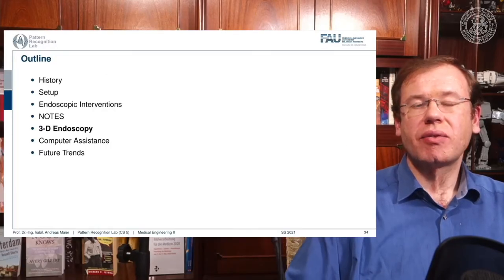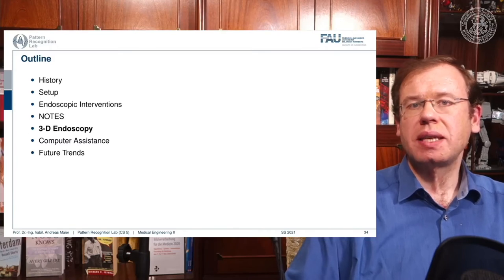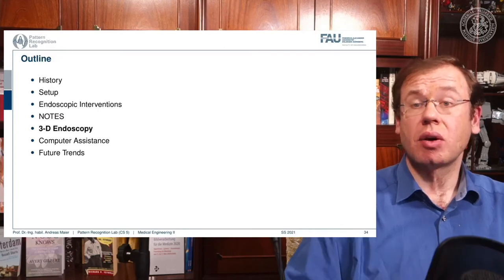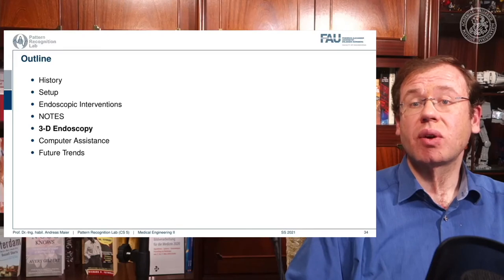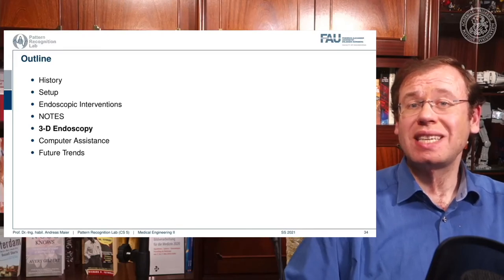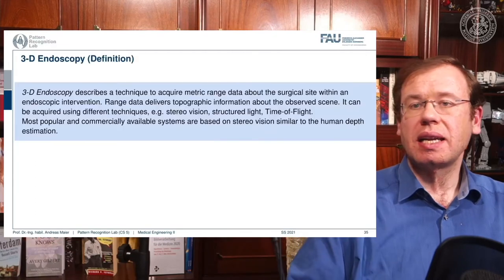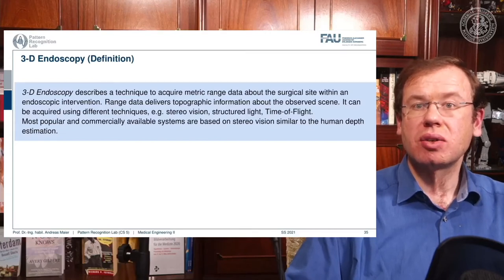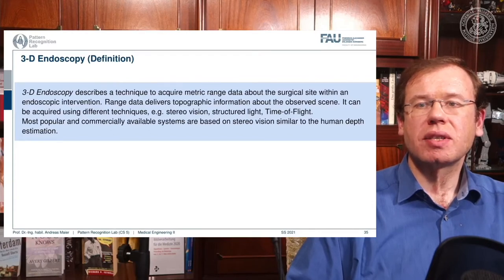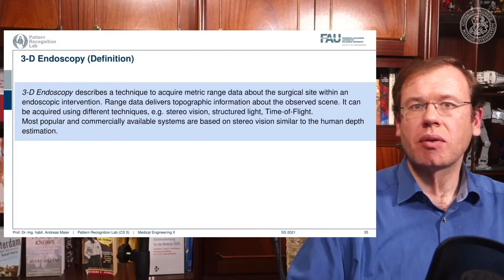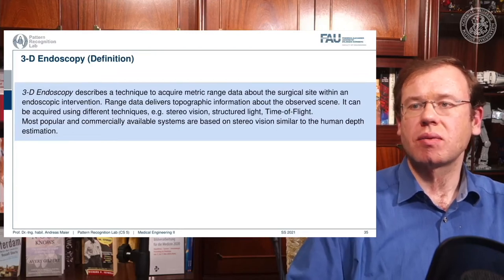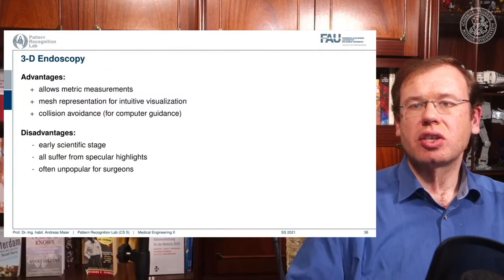Another very important topic is 3D endoscopy, which could be a game changer for complex interventions like NOTES. The idea is not just to see inside but to get a real 3D reconstruction of the tissues inside the body. In 3D endoscopy, we acquire metric range data — depth data like surfaces or point clouds of the surgical site — using an endoscopic intervention. This range data delivers topographic information about the observed scene and can be acquired using different techniques.